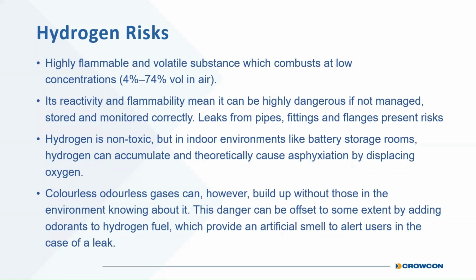Hydrogen is not toxic, but of course it can displace oxygen in air and thereby cause asphyxiation. It's less likely to do so than heavy gases, which collect from the floor up, because it collects from the ceiling downwards, and there's often vents high up and things like that in buildings. But it is possible to trap enough hydrogen in a room to not only cause a dangerous explosive mixture, but eventually to cause there to be not enough oxygen to breathe. Hydrogen is a dangerous gas, but if it's properly managed, it can be controlled safely.